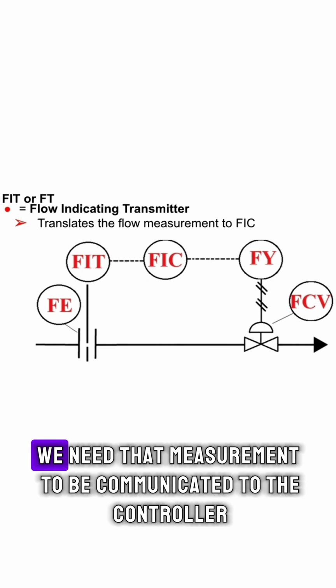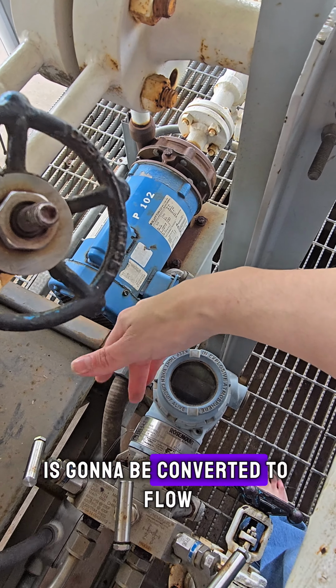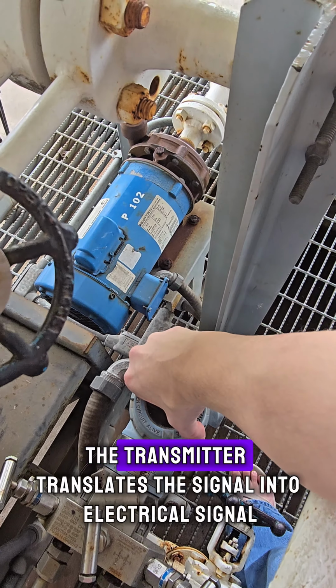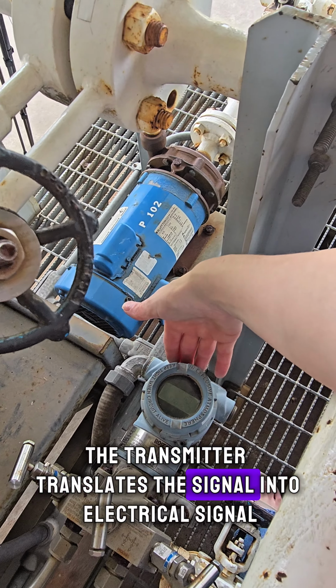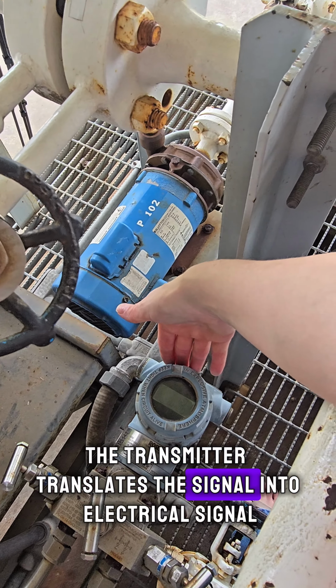those dashed lines represent electrical signal. And then the process, the two legs, are going to go into the transmitter, which is where that differential pressure is going to be converted to flow. The transmitter translates the signal into electrical signal so that our board can read it. So this is that electric wiring.